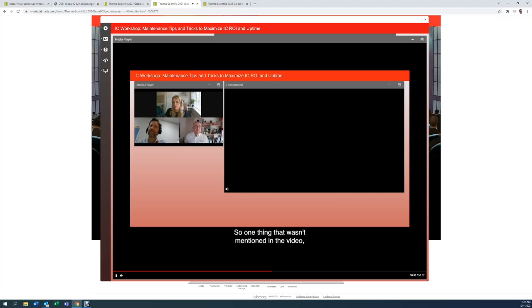Yeah, exactly. So one thing that wasn't mentioned in the video, but sometimes you have the filters in the bottom of the eluent bottle. Is there anything that people need to be aware of with those, regular changing or anything to look out for? Yeah, really good point, Gemma. The filters there are quite a coarse filter, and they're really there just to take out any precipitation and any undissolved carbonate that you've got in the bottle, and anything else that might have dropped into the bottle as you're making it.